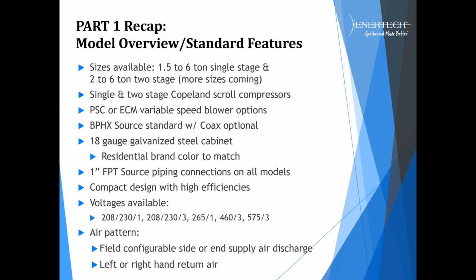This product features a heavy gauge steel cabinet, 18 gauge all the way around with a 16 gauge bottom panel with rail stiffeners, so it's a very robust cabinet, and we offer the residential brand colors to match the rest of the products in the residential sector. This product comes with 1-inch female pipe thread on all source piping connections. That's on all models. It's a very compact design with high efficiencies.